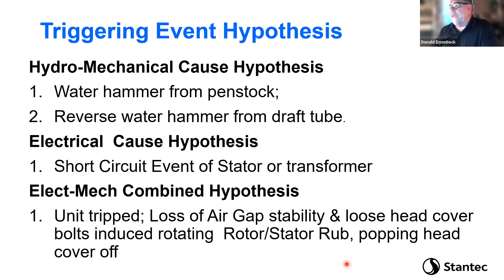that could have happened in the generator, because for those people who've ever worked in a big generator or big motor, once you synchronize, this motor acts like a giant electromagnetic bearing, and it tries to center the stator and rotor inside the machine on the electrical center of the stator. And so the machine can move a little bit from mechanical center to electrical center. And if it had tripped off for any reason, and all of a sudden the grid and load went away quickly, the air gap all of a sudden became unstable and the machine wants to go to mechanical center. And it can add a large load, and it can actually pull the rotor into the stator and have a small, let's call it a kiss rub between the rotor and the stator of the generator. Now, because of the bearing configuration, one of the theories is that led to that.